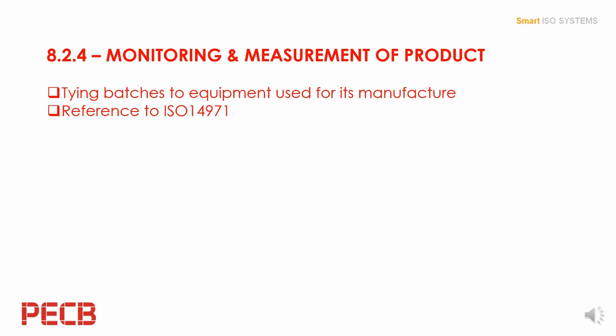This clause now includes a note that states records shall identify the test equipment used to perform measurement activities and the personnel authorizing release of the product. Every batch manufactured will require you to demonstrate what equipment was used. So if 10 measuring gauges have been used in the process, then you need to be able to trace them down to which one you used to measure some aspect of the device before its final release.